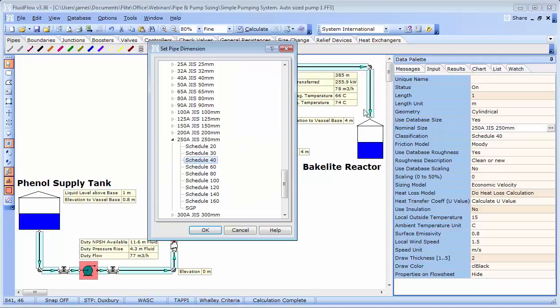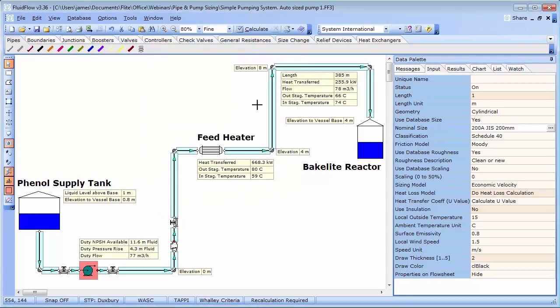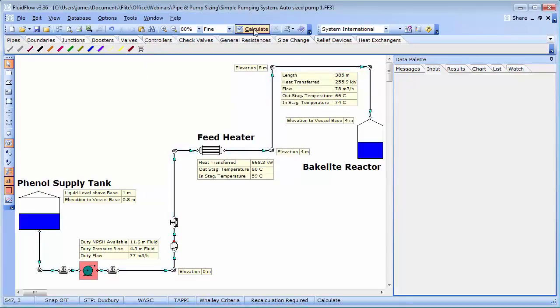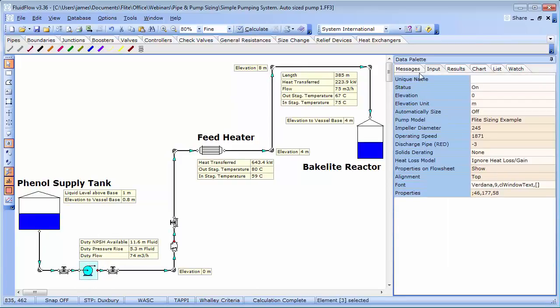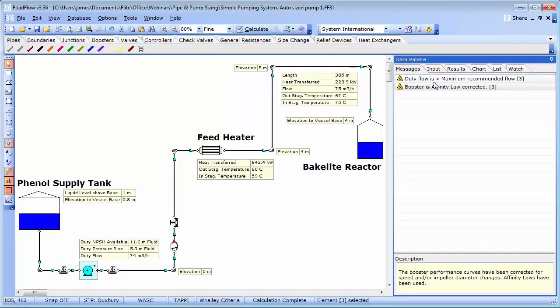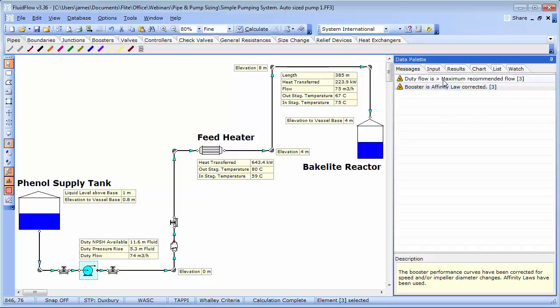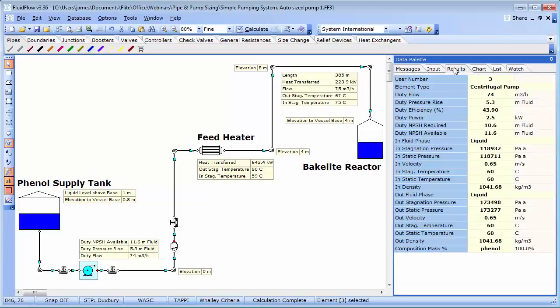So now we will make all pipes 200 mm in diameter. And let's see how efficient the solution is. So we still have a warning for the pump. We can have a quick look. So the warning is telling us once again the booster affinity laws have been applied. And the duty point is beyond the maximum recommended flow. Let's look at the results.